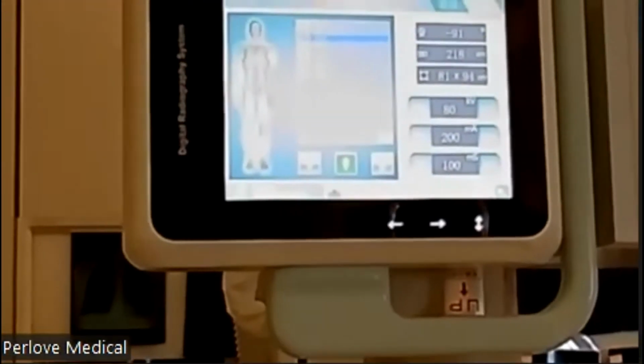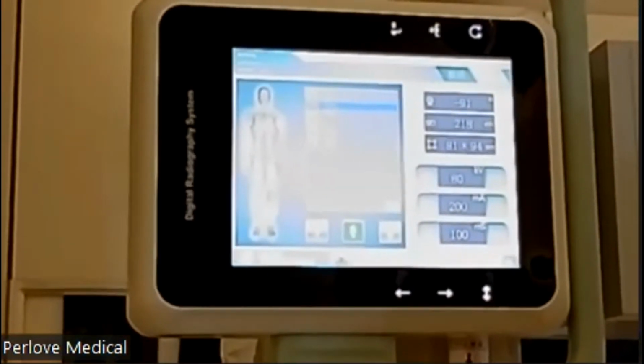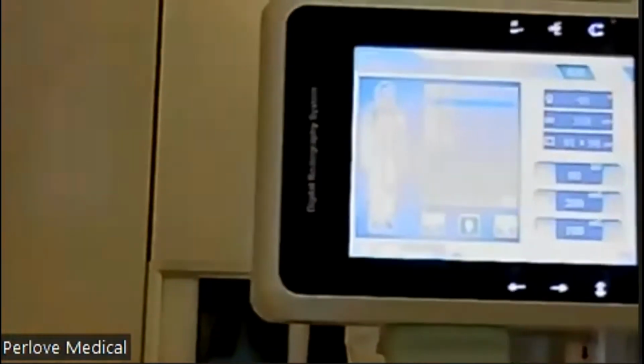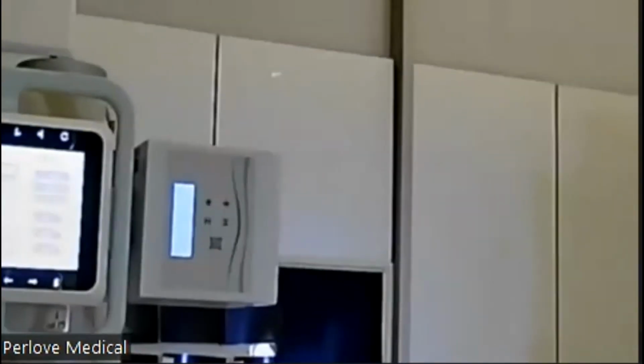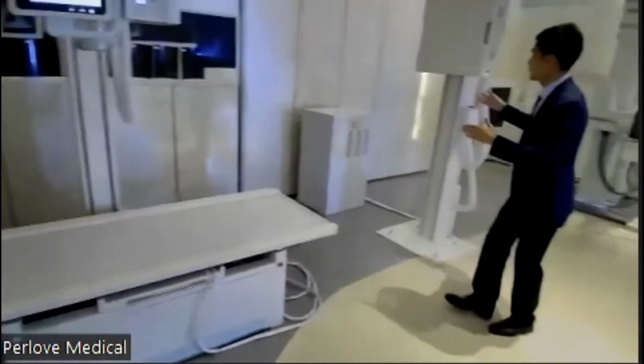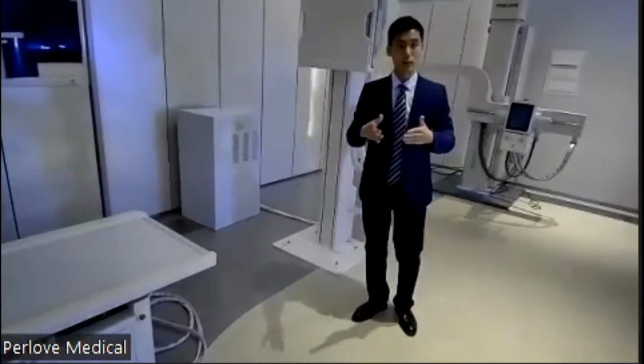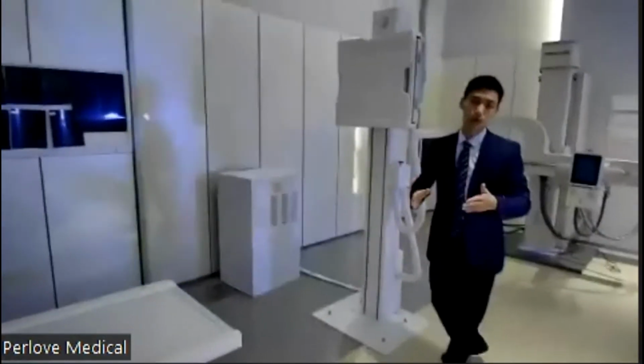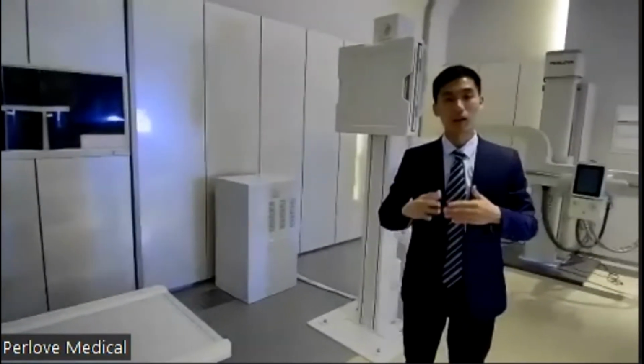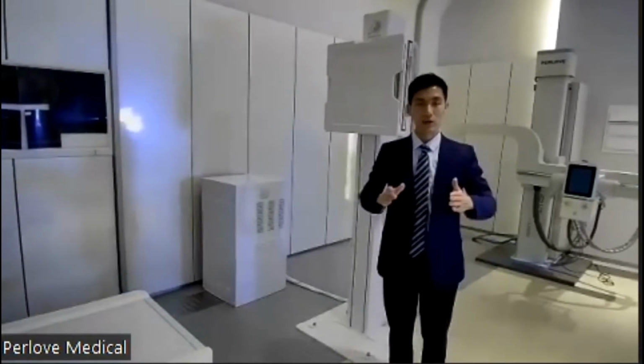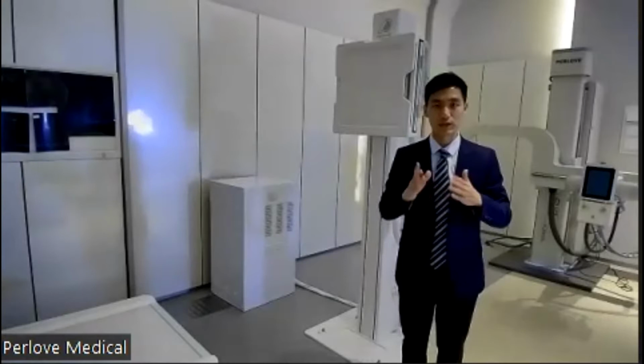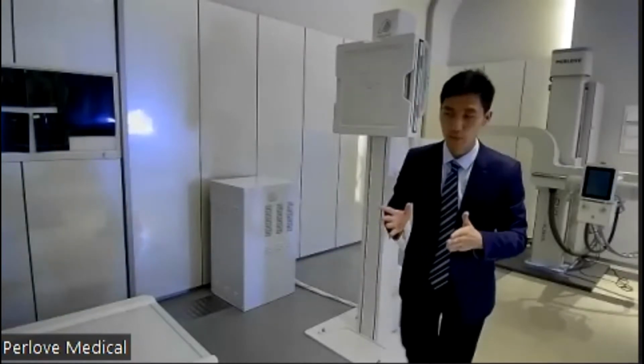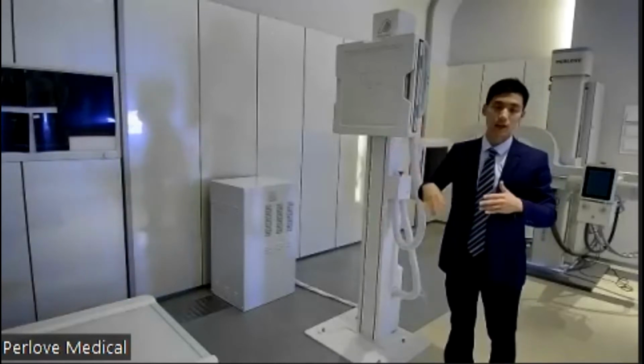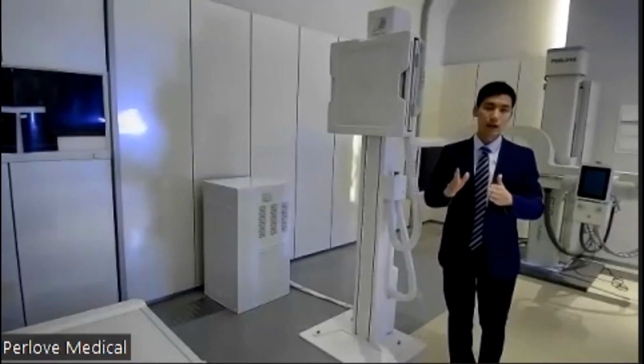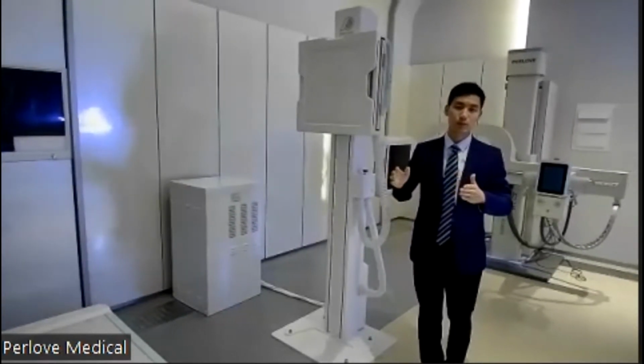And of course, as I have mentioned, this is a digital motion X-ray. We have mainly improved the flat panel detector. Now we have the dynamic flat panel detector for this machine. This machine has two cassettes. One is for the patient table, and the other is for the body stand. You can choose one flat panel detector or two flat panel detectors. As for the flat panel detector, I want to mention some latest technical innovations. Firstly, it was changed from static to dynamic. So the machine can be used for fluoroscopy now. And the parameters for the flat panel detector are outstanding. You can have 100 micrometers pixel size for the flat panel detector.